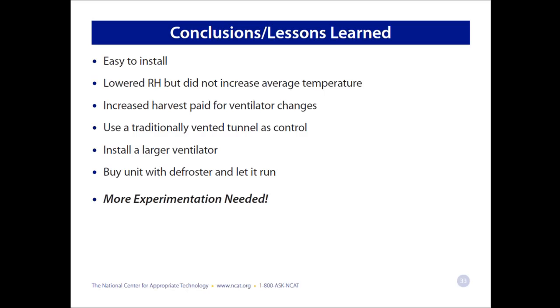So some of the conclusions and lessons learned, I talked about some of these as we went through the webinar, but the unit itself was fairly easy to install. It was not very costly compared to the type of production numbers that are coming out of these high tunnels. It did lower the relative humidity, but it did not increase average daily temperature inside the high tunnel compared to the control tunnel. And it didn't hit our 85% mark that we were shooting for, 85% relative humidity or lower. We did not achieve that.